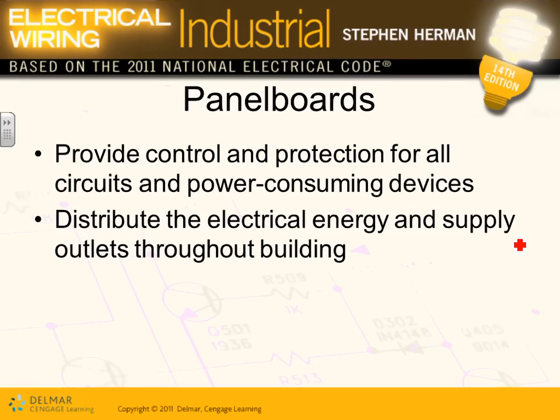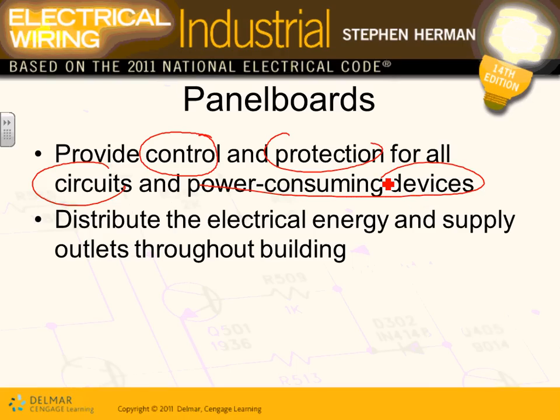What do the panels do for a living, guys? They do two things. When you have a panel, you guys have done it. First, they control. Second, they protect all the circuits and deliver the power to the devices. So they deliver, and here's the panel. It's like a busway. The panel, what does it do? Deliver the power to the system, to you, if you're a load, and the lights. And in the process, it controls it, so you can turn them on and off through a circuit breaker if you want to, and protect them from short circuit. Deliver power, control, and protect. Does that make sense? That's what panels do, exactly like a busway does.